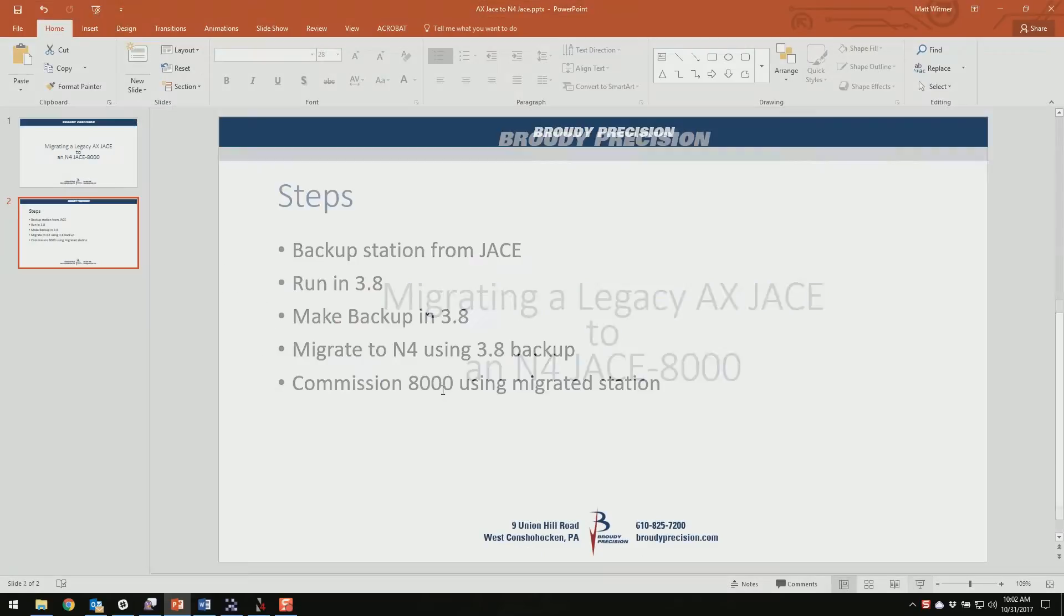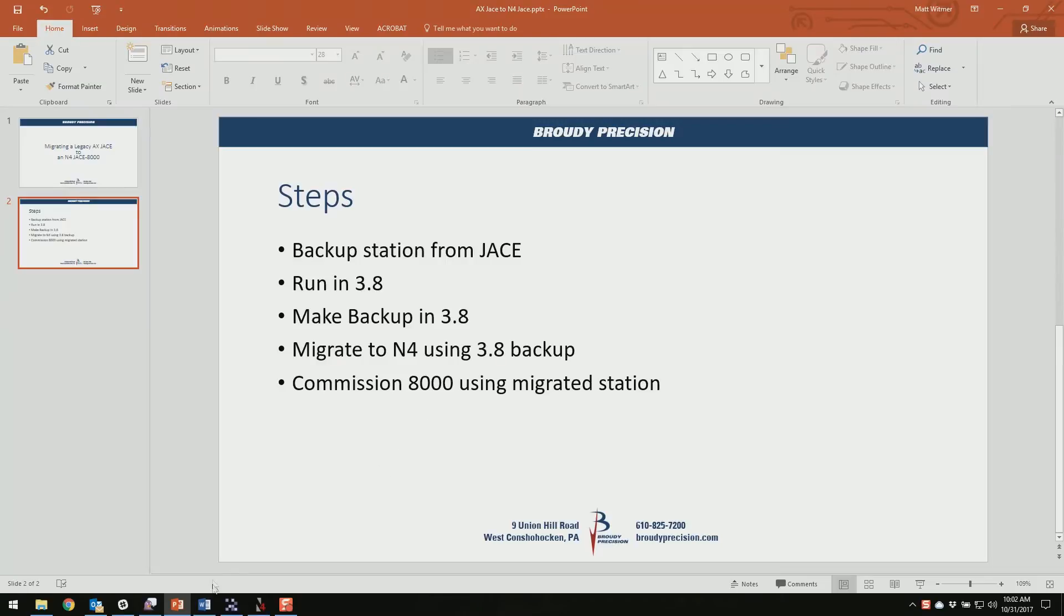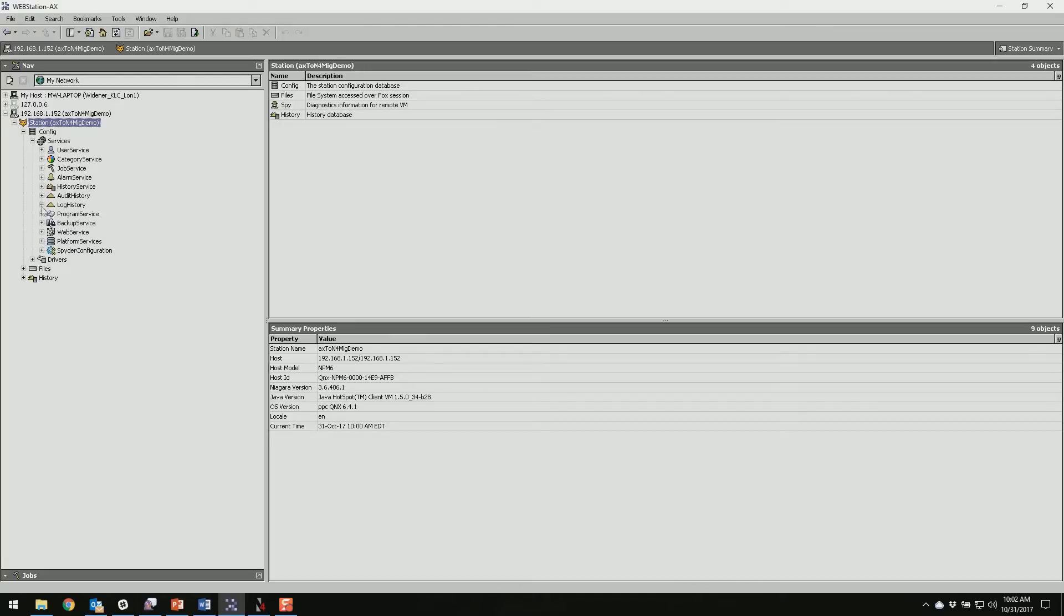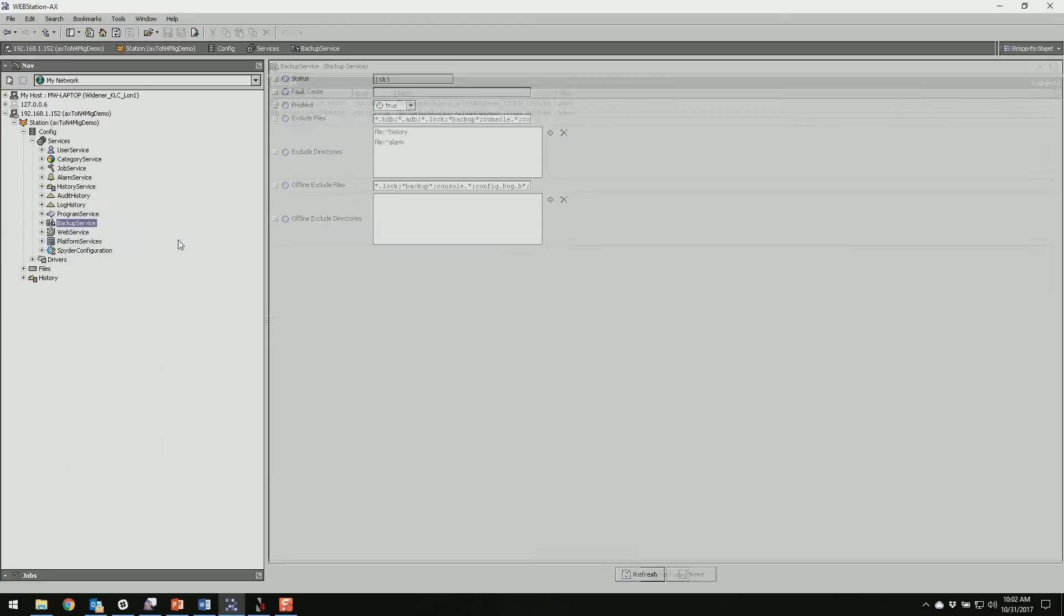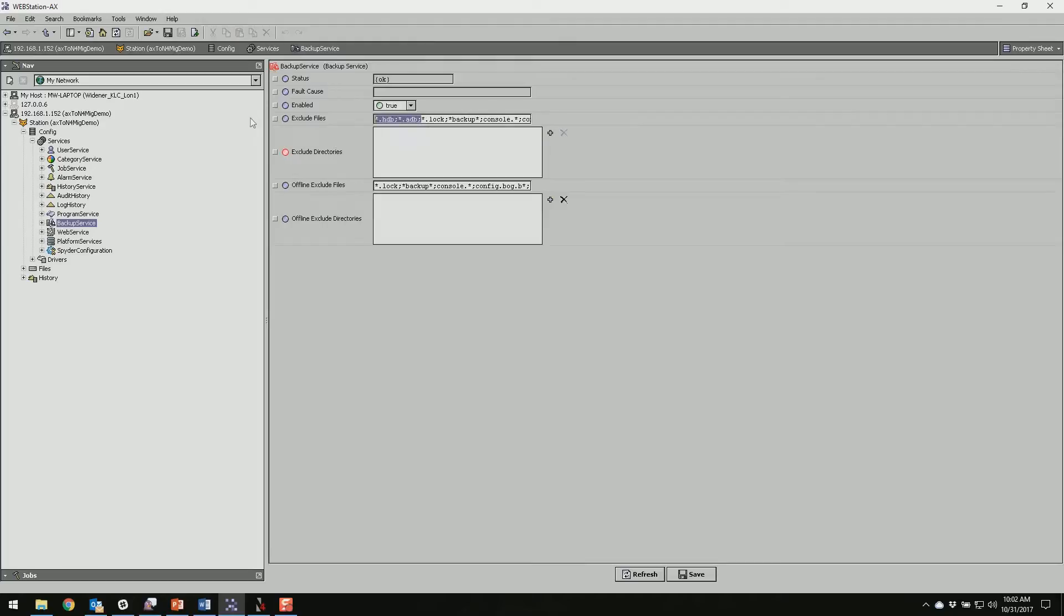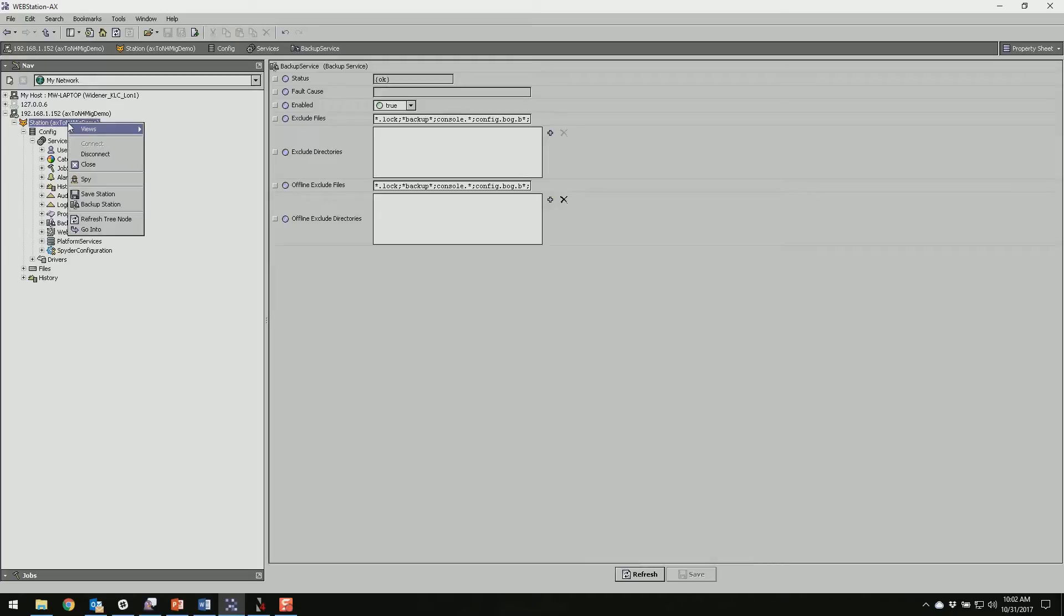So our first step is to log into our Jace and make a backup. Before we do that though, we need to make sure that we're including our histories and alarms. So we need to go into our services and the backup service and the property sheet of the backup service and get rid of these exclusions in both the directories and the files. We'll get rid of these and save, and now we can right click on our station and do a backup.